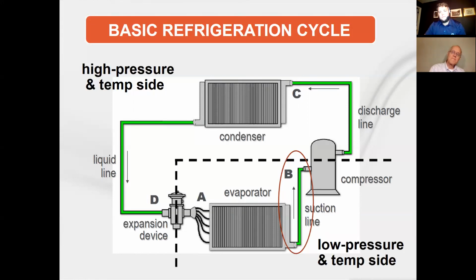I'll get another question here. We normally do not see hot gas reheat options in split systems as we see them in packaged DOAS units. Why is that? Well, it's hard enough to design a piping system with just these two pipes, and it all gets down to refrigerant management and oil management, and I'm not saying it can't be done. It's just very difficult to put something like that on a drawing, whereas the ones we do in the factory, we've done hundreds of them and we know how it works, and they've tested that in a laboratory setting and they know what the limitations are.